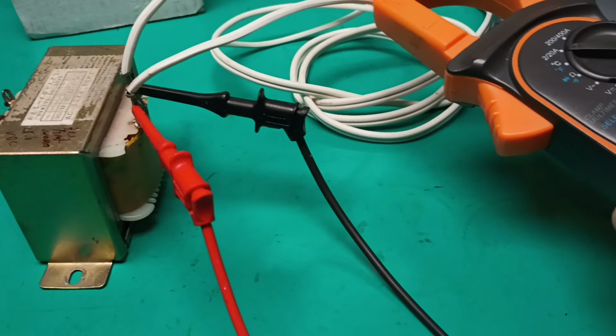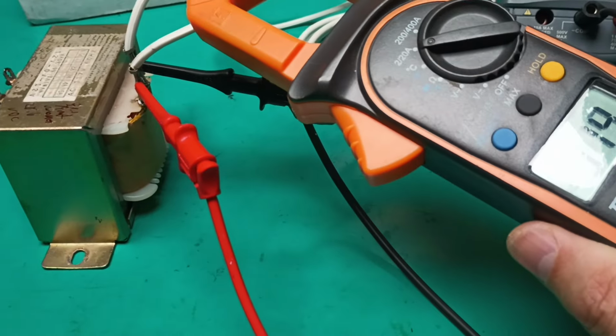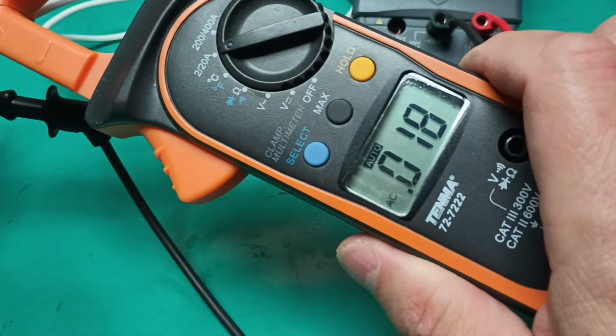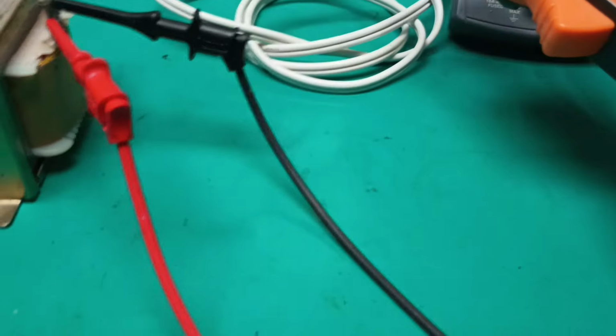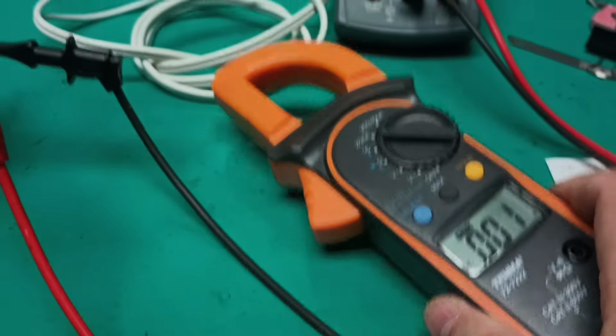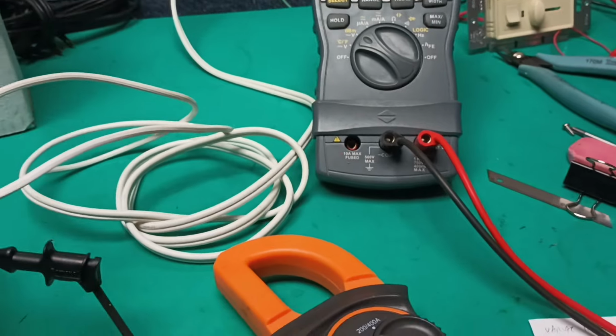So if using a current clamp to measure the AC line here, you've got to make sure the current clamp is far enough away not to have that current added, because that'll cause a real error in the actual current of the transformer. This measures about 79 mils. I used the meter. It's actually 75, close enough.